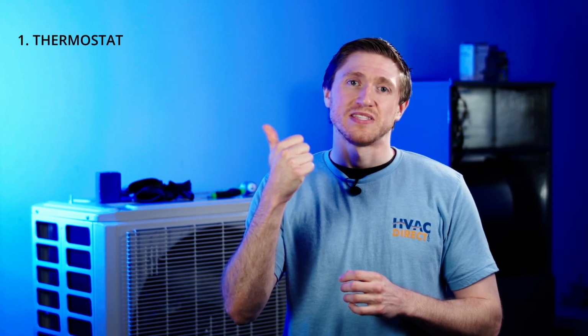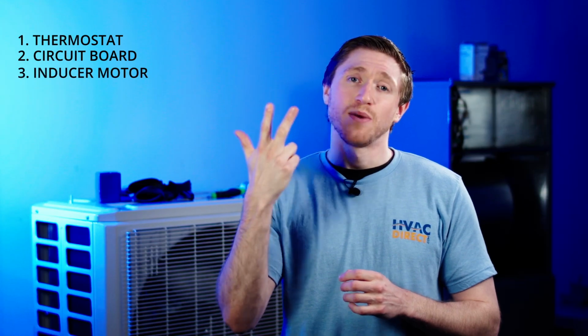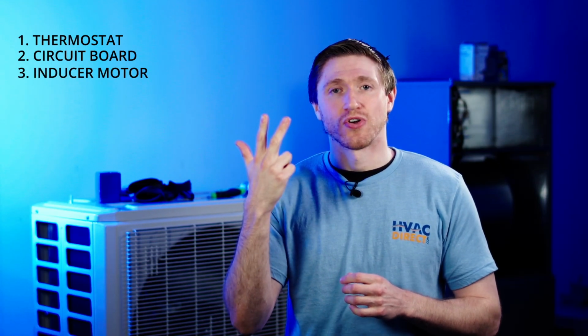So to go over that one more time for you, we'll walk you through the 11 things that you can check, or your service technician should check, depending on the item, if your furnace isn't operating. Number 1, check the thermostat. Number 2, your technician should make sure that the circuit board is getting proper voltage and has no issues. Number 3, your inducer motor should turn on. This is one that you'd be able to visually see.